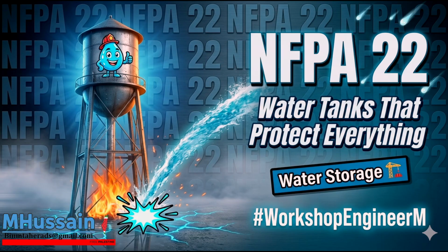Yeah, that failure isn't theoretical. It is the ultimate nightmare scenario in fire protection engineering, and I mean, it happens. It really does. You can have the most advanced hydraulic distribution network in the world, but it entirely relies on the fundamental assumption that water will just be there at the required pressure in the necessary volume, the exact millisecond that impeller starts spinning. And when engineers treat the water tank as just a static bucket rather than a dynamic engineered machine, that's when those critical failures occur.